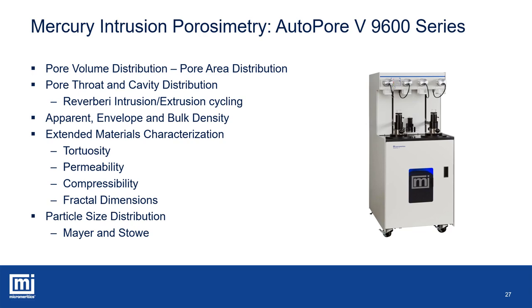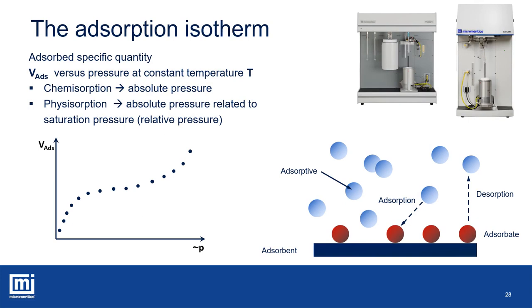Gas adsorption is probably the most widely used technique to measure the exposed surface area of solid materials and powders. It measures pore sizes in the micro and mesopore range and is generally performed under isothermal conditions. Adsorption is a phenomenon that involves a higher density of gas molecules in proximity to solid surfaces due to the free surface energy of atoms and molecules in the solid surface which are not bounded by other molecules. The free surface energy is quite weak, in the order of van der Waals forces. At relatively high temperatures like room temperature, gas molecules have high kinetic energy compared to the free surface energy, so the amount of gas adsorbed on flat surfaces cannot be conveniently measured.